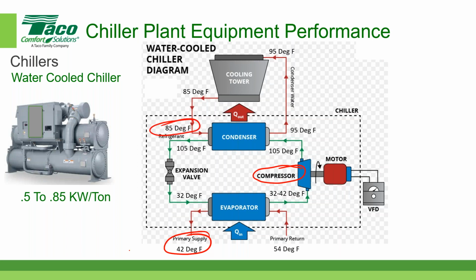So if I can raise my chilled water temperature, that means that I can raise my refrigerant temperature. If I can lower my condenser water temperature, I can lower my refrigerant temperature at the high end, and that temperature difference and the pressure associated with that is called lift, L-I-F-T. So the compressor is adding pressure to the system as a function of these temperatures.